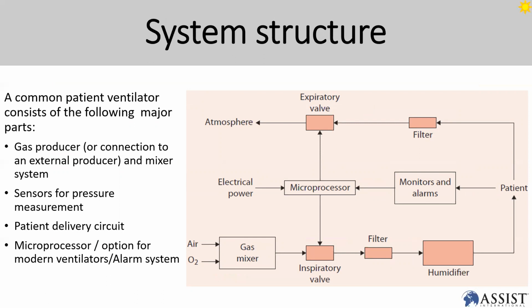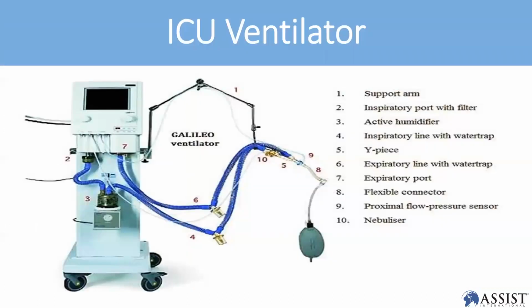You need to know what I explained earlier: gas mixing, inspiratory valve, flow, all this. And the sensors on the expiratory valve and inspiratory valve play a very important role. Then patient delivery circuit, microprocessor with the monitoring alarm system. So when you talk about an ICU ventilator, you're talking about number one, support arm; number two, inspiratory port with the filter; then number three, active humidifier; number four is inspiratory line with the water trap, and Y-piece, some use T-piece type; expiratory line with water trap on number 6 as well. Flexible connector, then flow pressure sensor, nebulizer, all these you're normally going to see in the ICU ventilator.